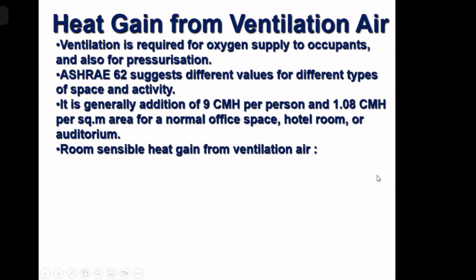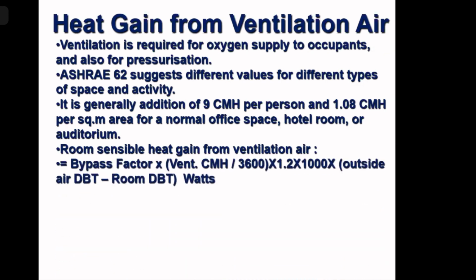So once we have decided on how much ventilation air, now we must calculate how much part will be sensible heat, how much part will be latent heat from there, and how much will come directly inside the room. 12% will come directly inside the room because of the bypass factor of the cooling coil, and 88% will go in the cooling coil. So room sensible heat will be bypass factor, that is 0.12, into ventilation CMH, that is 1116 CMH, divided by 3600, into 1.2 into 1000, into outside air dry bulb temperature minus room dry bulb temperature. So much watts. This will be coming directly inside the room as sensible heat.